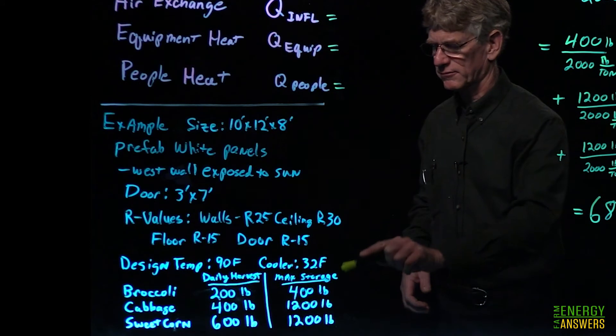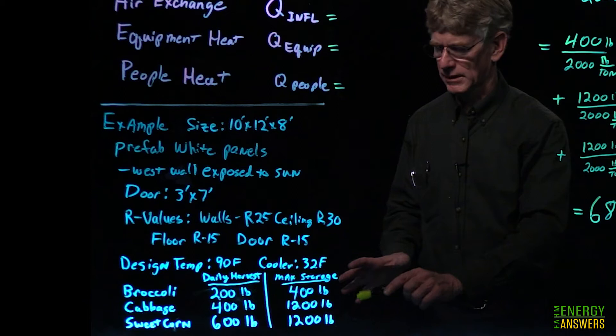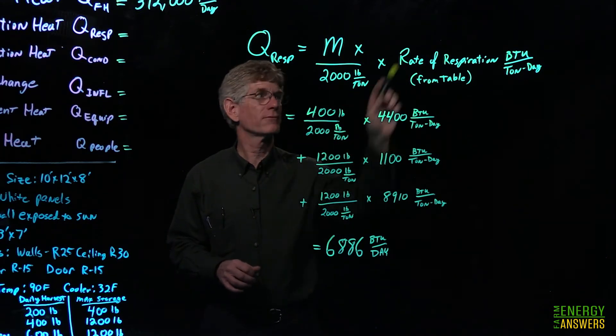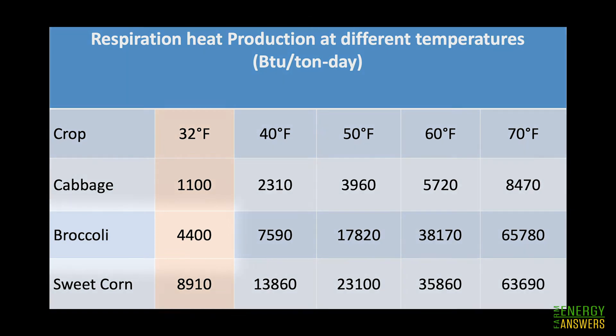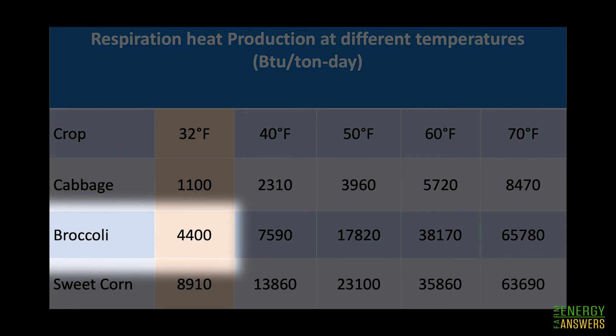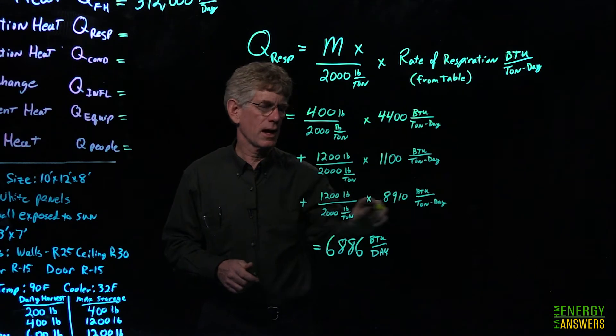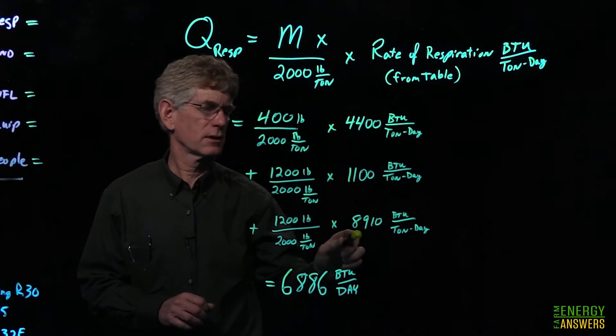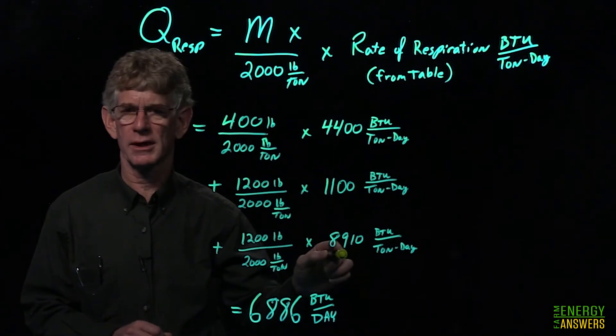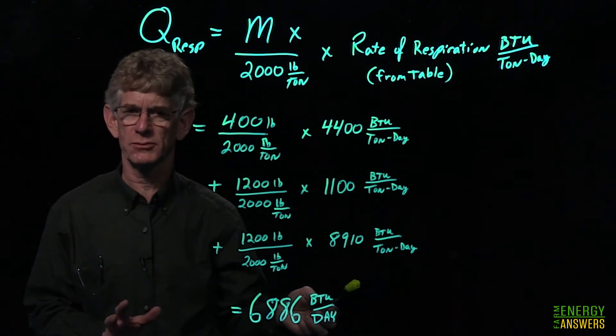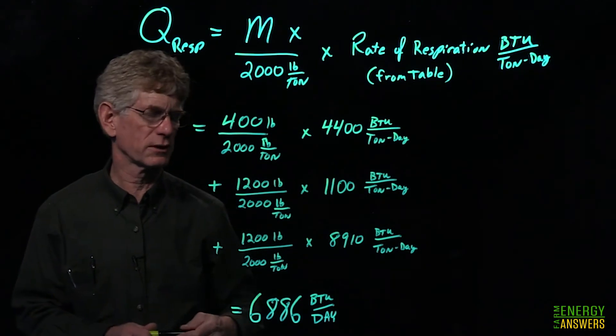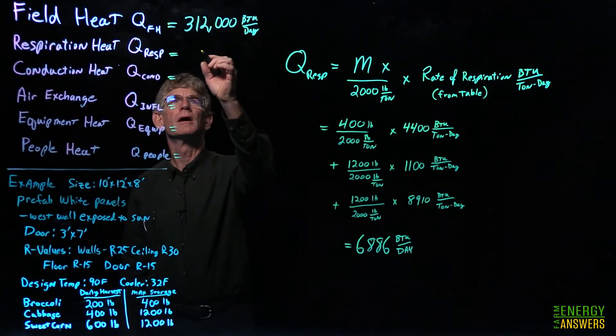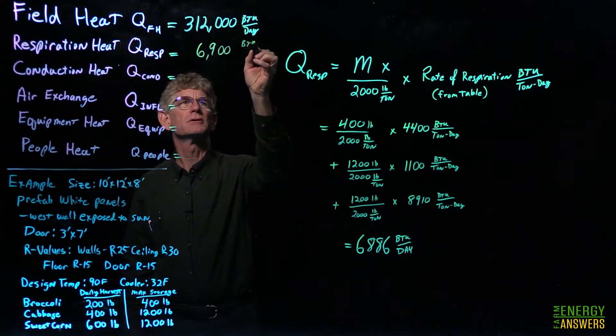In our example, we look at the amount of produce stored in the cooler at any one time. For broccoli: 400 lbs ÷ 2,000 = 0.2 tons, and from the chart at 32°F, broccoli has a respiration rate of 4,400 BTUs per ton per day. We do the same for cabbage and sweet corn. One important note: sweet corn generates about nine times more heat than cabbage at 32°F, so you must be aware of what you're storing. In total, we get about 6,900 BTUs per day from respiration heat.